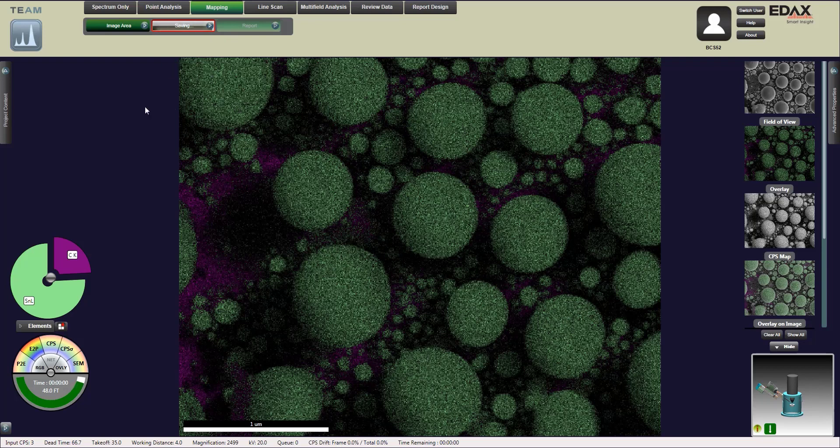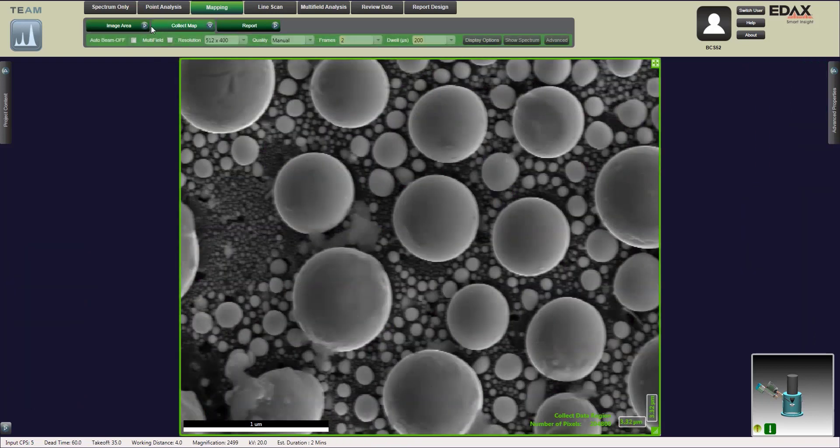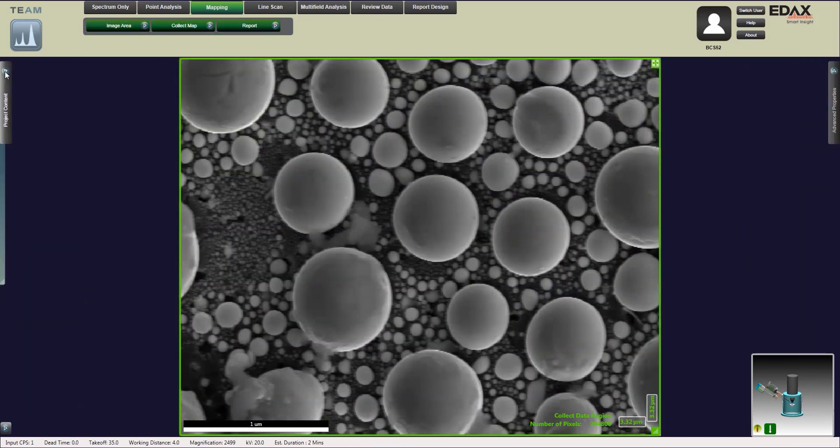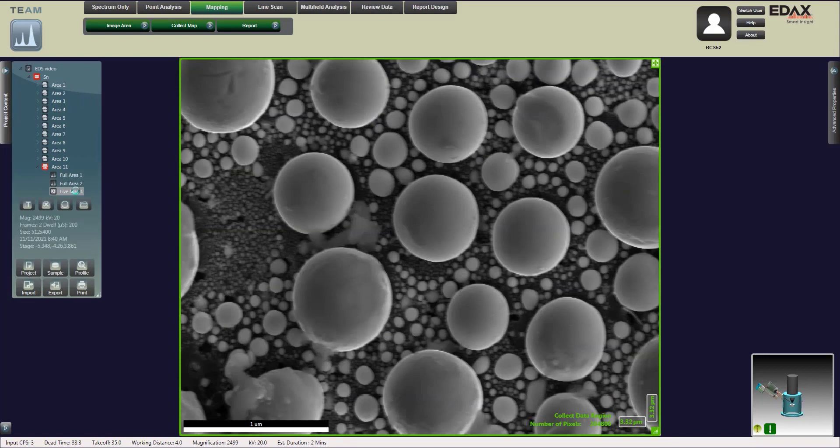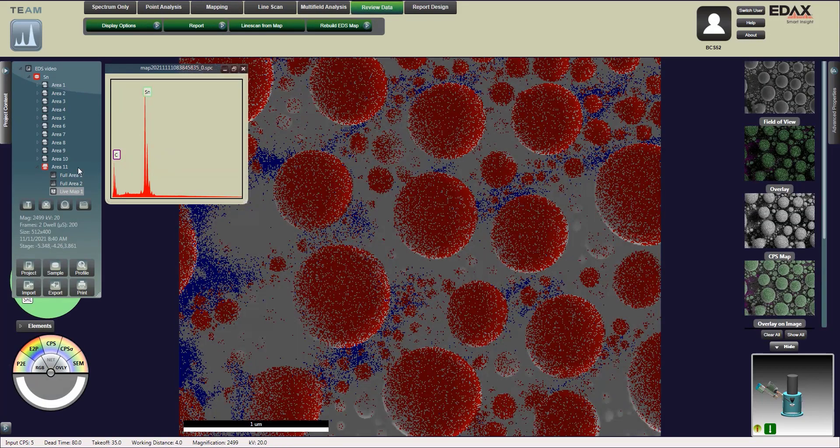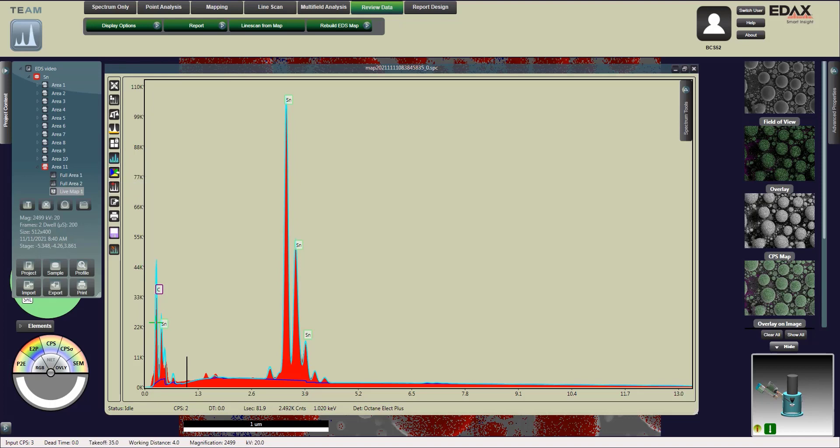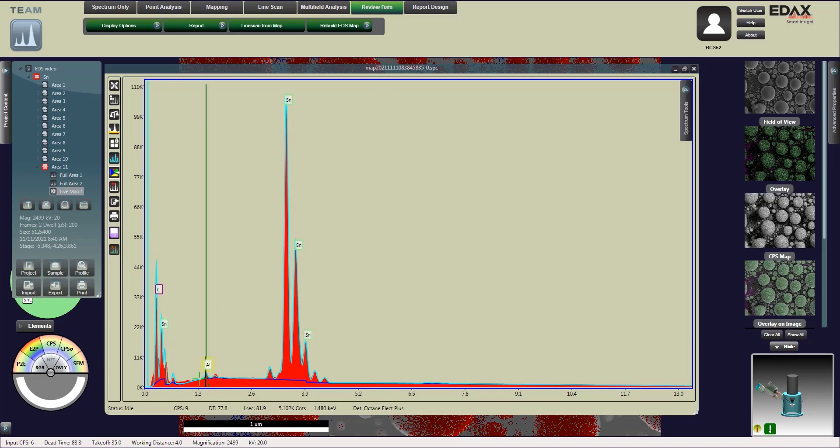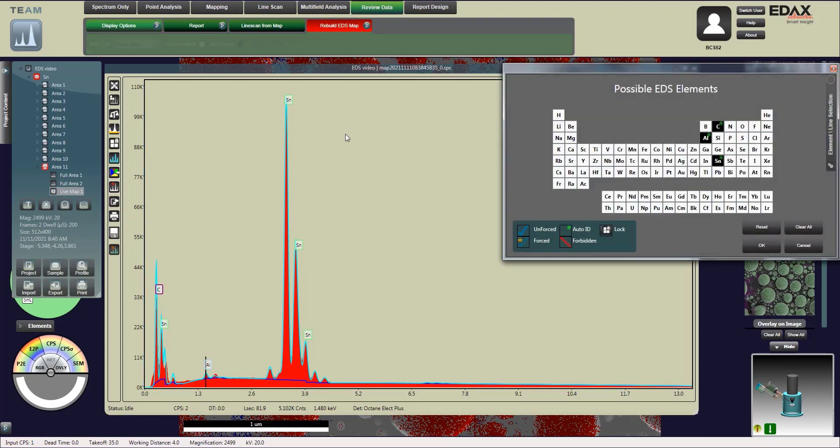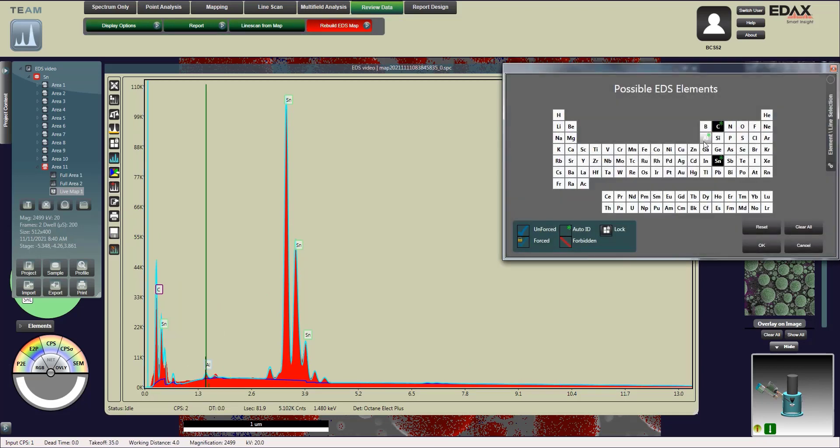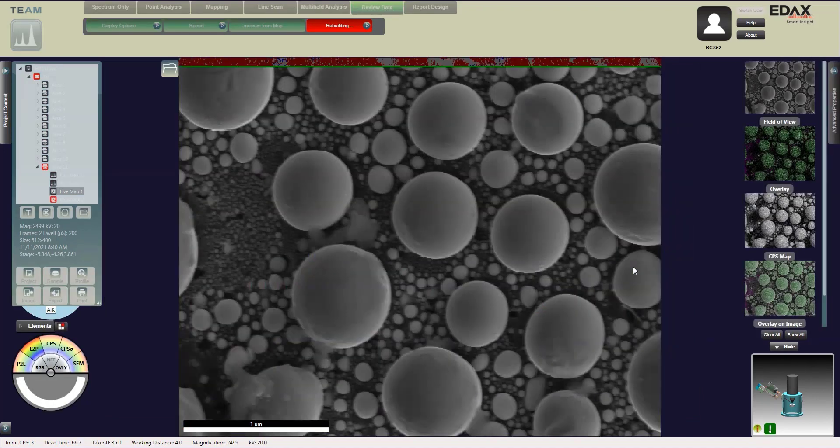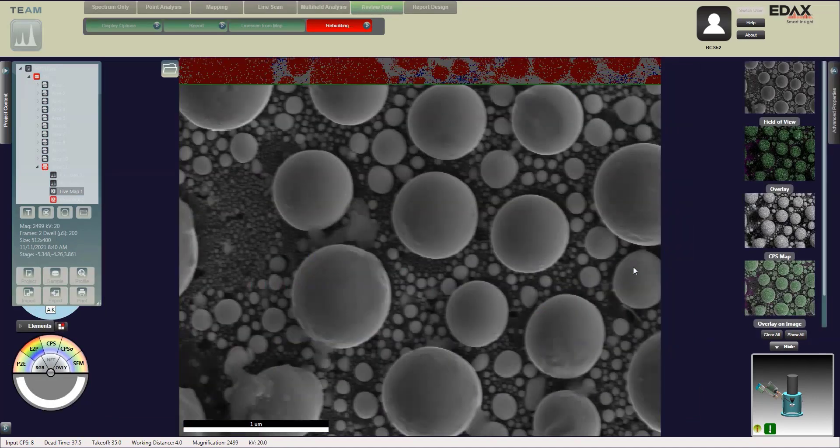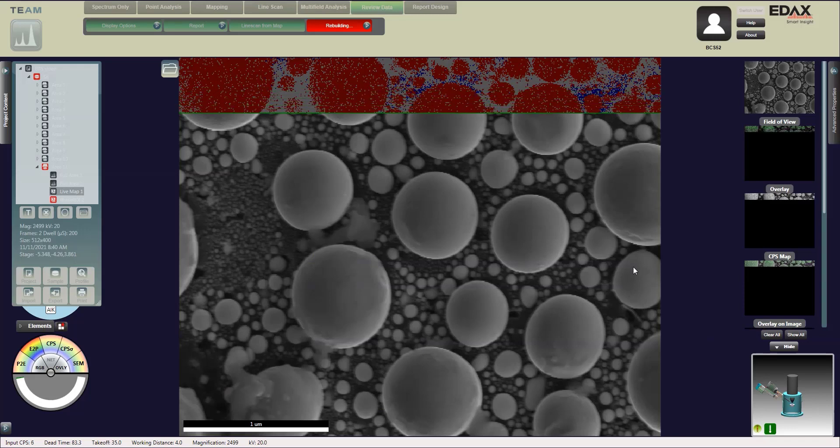We'll click finish on that and if we want to review we can open up project content, click on the live map that we just took. We can do any manipulation of the elements that we need to do. We're going to check the background and the peaks and we're going to throw in, put back in our aluminum and then save that element. Now it's different here, it just doesn't automatically do it. We do have to rebuild the map. We're going to add our elements to the rebuild and it's going to scan over this a little bit slower the second time will be real quick to reposition our elements and those colors that we changed.